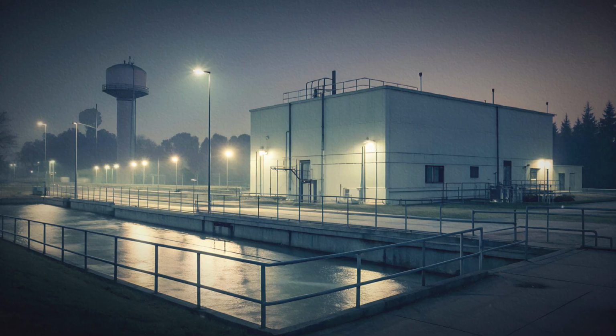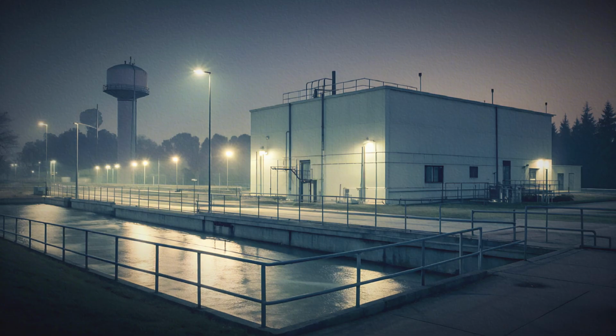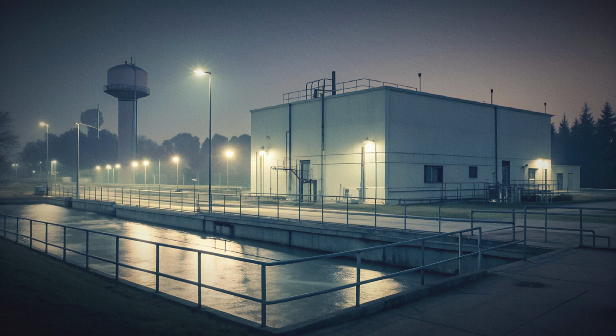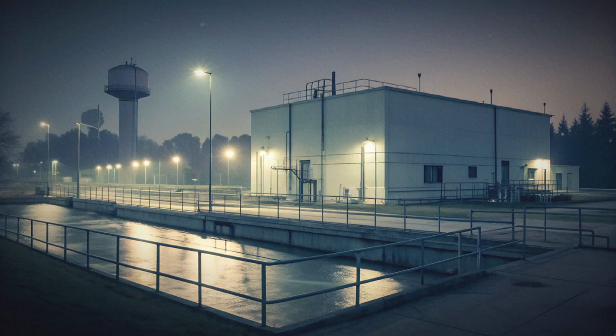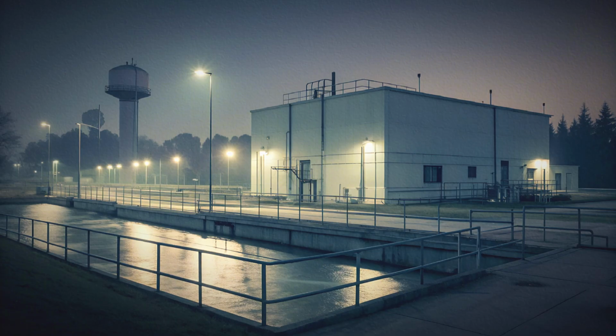Pumps, filters, and chemical dosing trains are often arranged in parallel. If one unit requires shutdown, the parallel units carry the load. This permits maintenance without loss of treatment capability. Physical redundancy includes parallel process trains and bypass lines. Parallel trains allow flow to be shifted from one set of tanks to another. Bypass lines provide a route around a specific unit. By closing and opening valves, flow is rerouted while work proceeds.